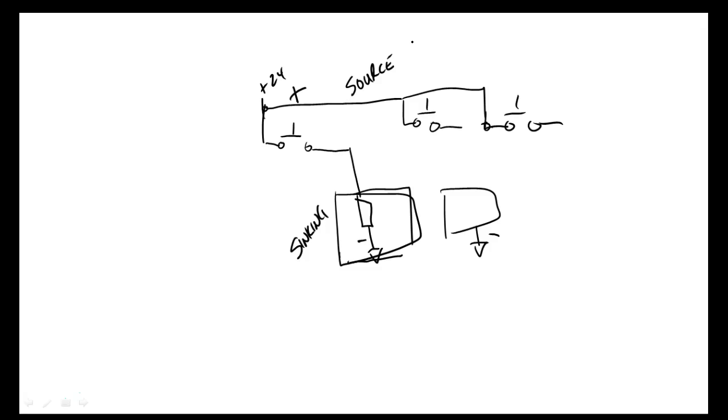If you take intro to PLCs, go back and look at the 504s, and you look at that input module, written plain as day, it says sinking on there. So on a modular PLC, a DC input module, you have to specify either what, sinking or sourcing. The Allen Bradley PLCs, we can hook them up either way, but you do it in a group. Depends on what you decide is common.